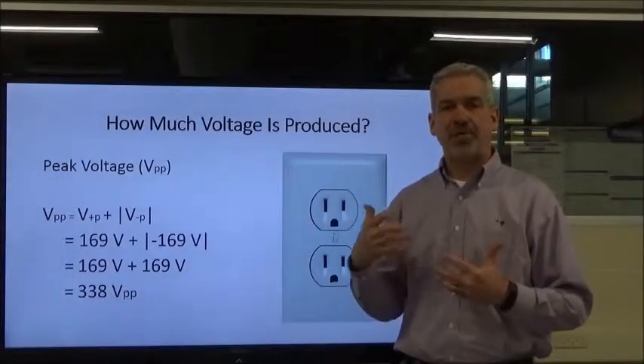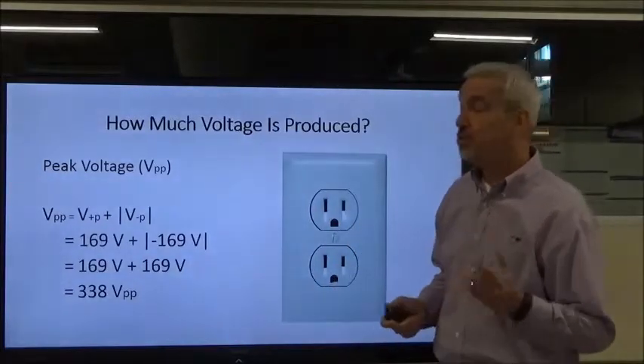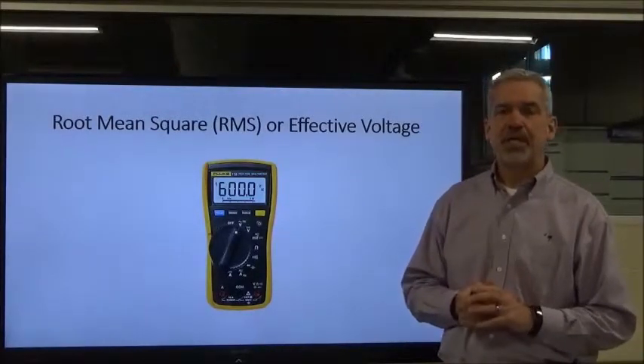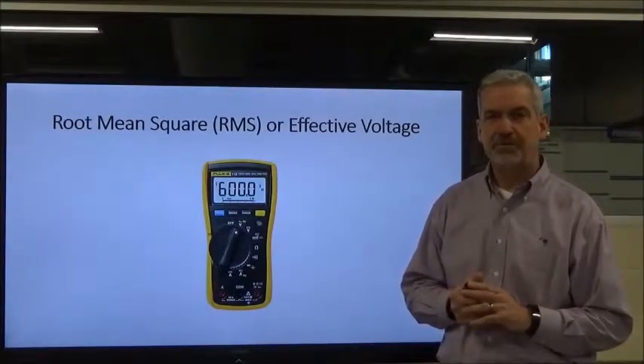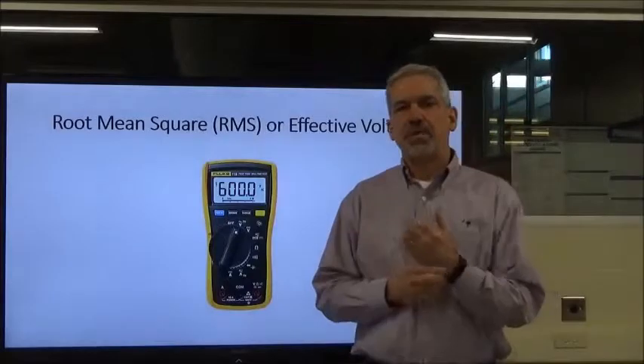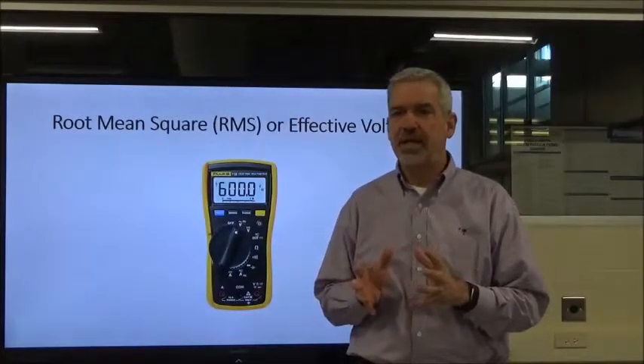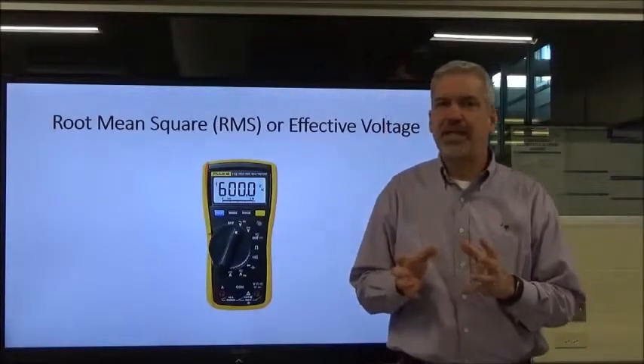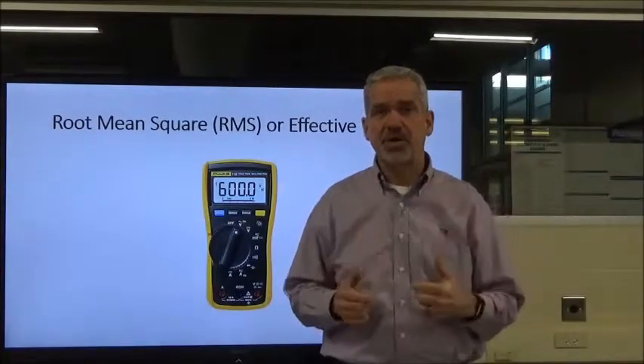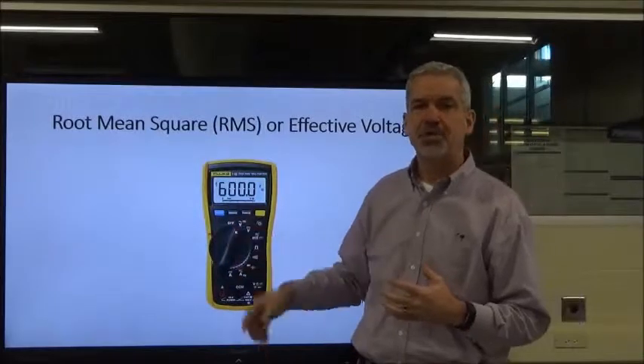I want you to stop this at some point and practice these formulas, make sure you're taking notes and that you understand them — you will see them again. Our multimeters measure the true RMS reading, not peak-to-peak or peak. One reason we would measure peak is using an oscilloscope. We often do that to measure the quality of power coming into a facility — particularly with sensitive electronics that may be affected by spikes, power imbalance, or phase issues. The oscilloscope lets us measure peak-to-peak and peak voltage to assess the condition of the power coming into our facilities.